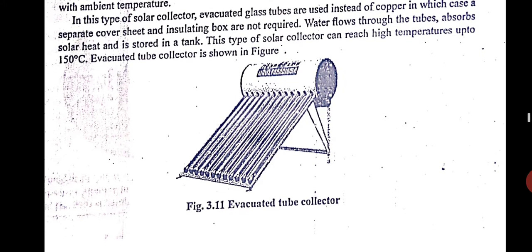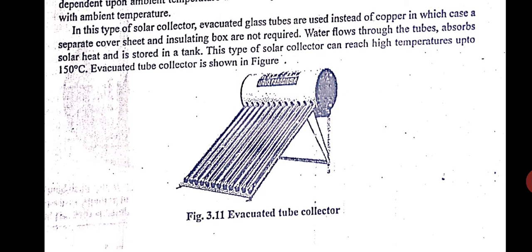In this type of solar collector, evacuated tubes are used instead of copper tubes. In this case a top glass cover is not required and also the insulation box is also not required. Water flows through the tubes, absorbs solar heat, and is stored in the tank. This movement of water is through gravity and thermosiphon effect only - there is no pump here.